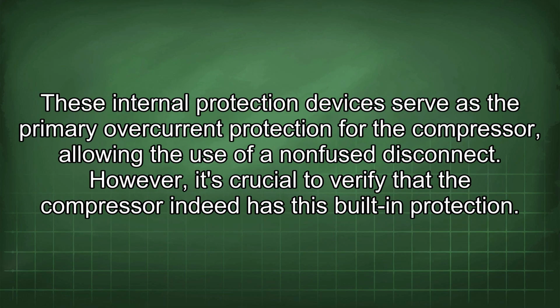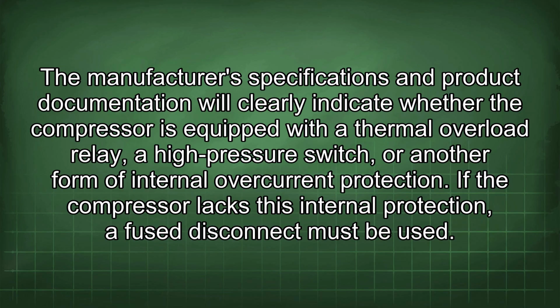These internal protection devices serve as the primary overcurrent protection for the compressor, allowing the use of a non-fused disconnect. However, it's crucial to verify that the compressor indeed has this built-in protection. The manufacturer's specifications and product documentation will clearly indicate whether the compressor is equipped with a thermal overload relay, a high-pressure switch, or another form of internal overcurrent protection. If the compressor lacks this internal protection, a fused disconnect must be used.